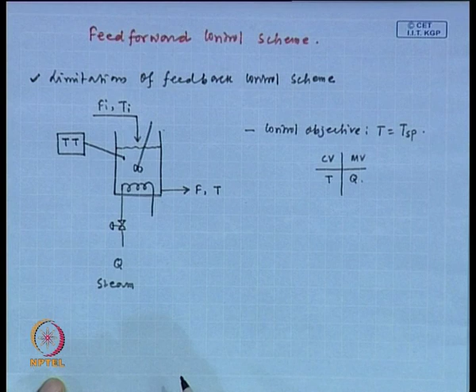Fine. So, what is the control objective? Control objective is to maintain temperature at its set point value. So, we can say that temperature is the controlled variable and corresponding manipulated variable is steam flow rate, that is Q. Fine. Now, we wish to employ one feedback control scheme. First, we need to measure the temperature by using a temperature measuring device denoted by TT. Then that measured signal is compared with set point value. Then this signal is used to calculate the control action, and then this action is implemented through the control valve.